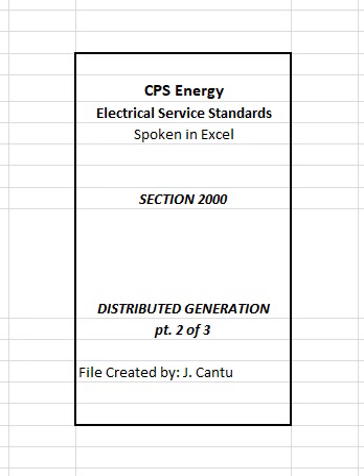B. Parallel operation. Customers' DG facilities shall be equipped with the necessary protective hardware and software designed to prevent connection or parallel operation of DG equipment with CPS Energy's distribution system unless the CPS Energy voltage and frequency is of normal magnitude. C. Metering/measuring energy at DG facilities. DG facilities shall have provisions and necessary equipment to measure both the energy produced by the DG facility (PV meter) and any energy provided by CPS Energy for customers' use (PV billing meter) at DG sites.